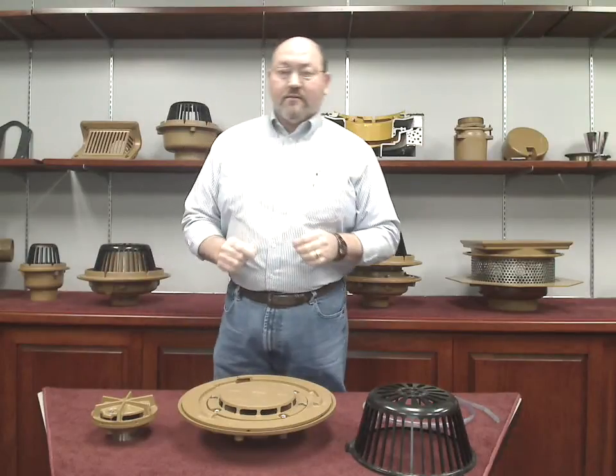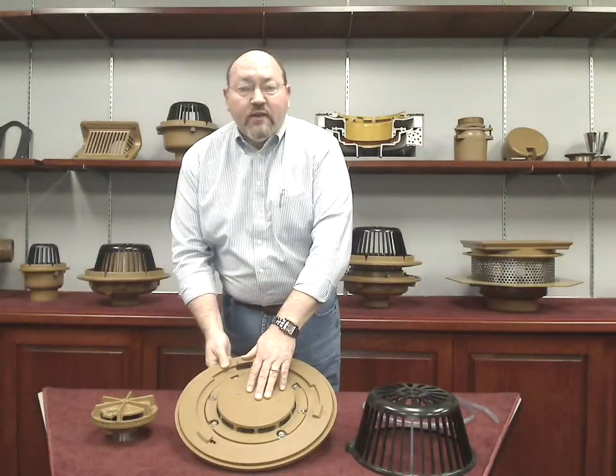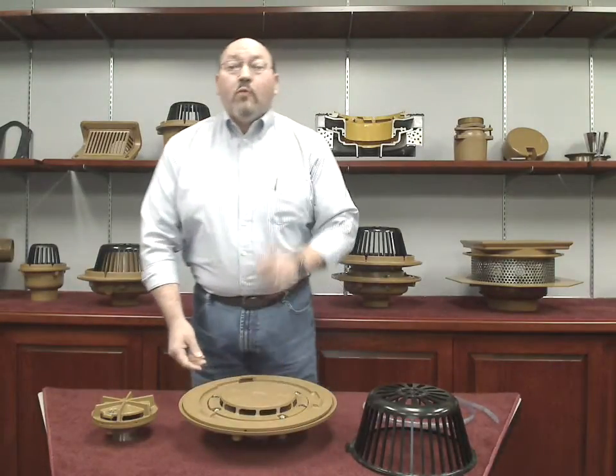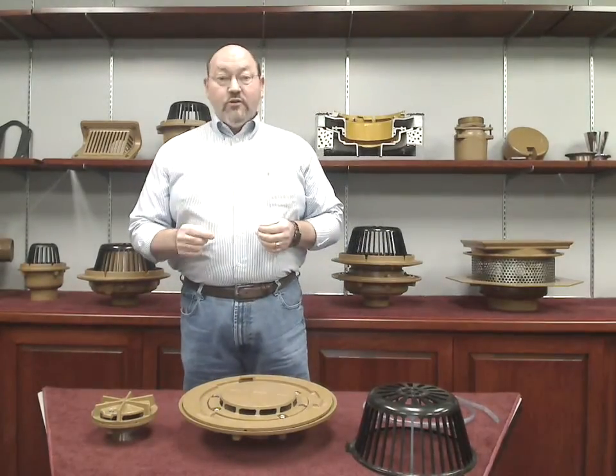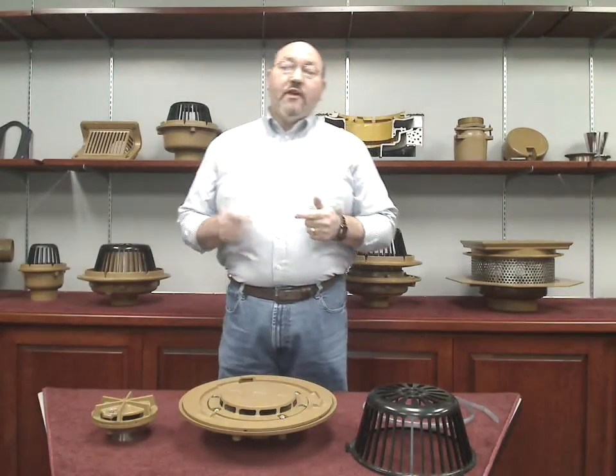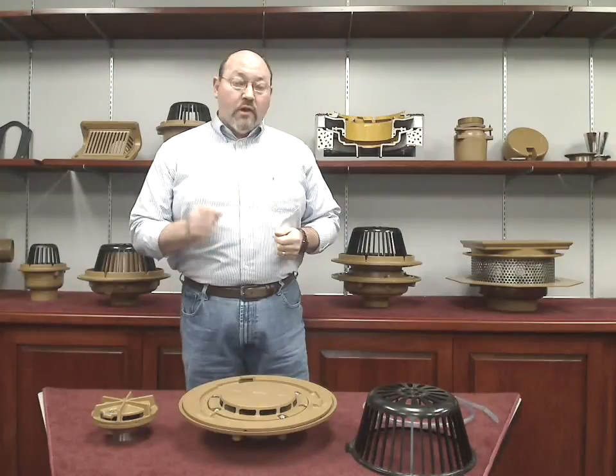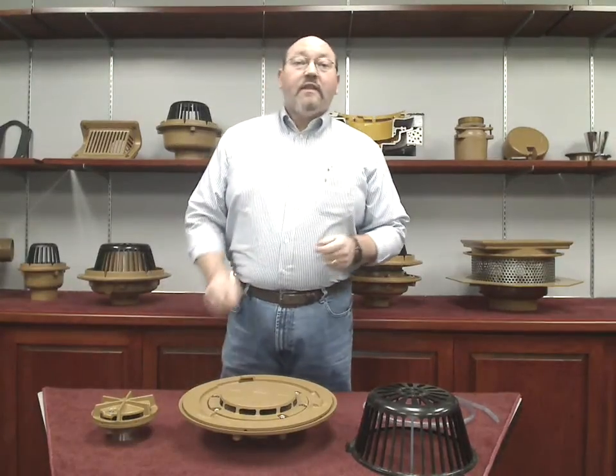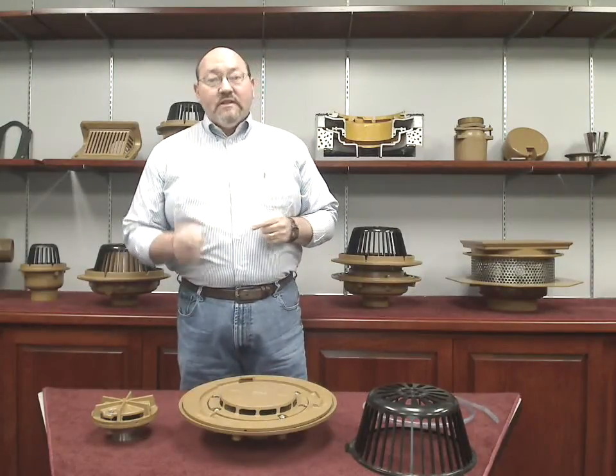Now let's look at a siphonic system. A siphonic system is a closed system, meaning that the air flow is shut off by the air baffle, causing the piping system to completely fill with water. When the piping system primes, it depressurizes, meaning the water pressure through the system is reduced due to the effect of gravity on the vertical drops. When this occurs, atmospheric pressure begins to push the water into the drains with a force of 14.7 pounds per square inch. The capacity of a siphonic system is determined by the piping system itself and the height of the roof drain above the point of discharge.